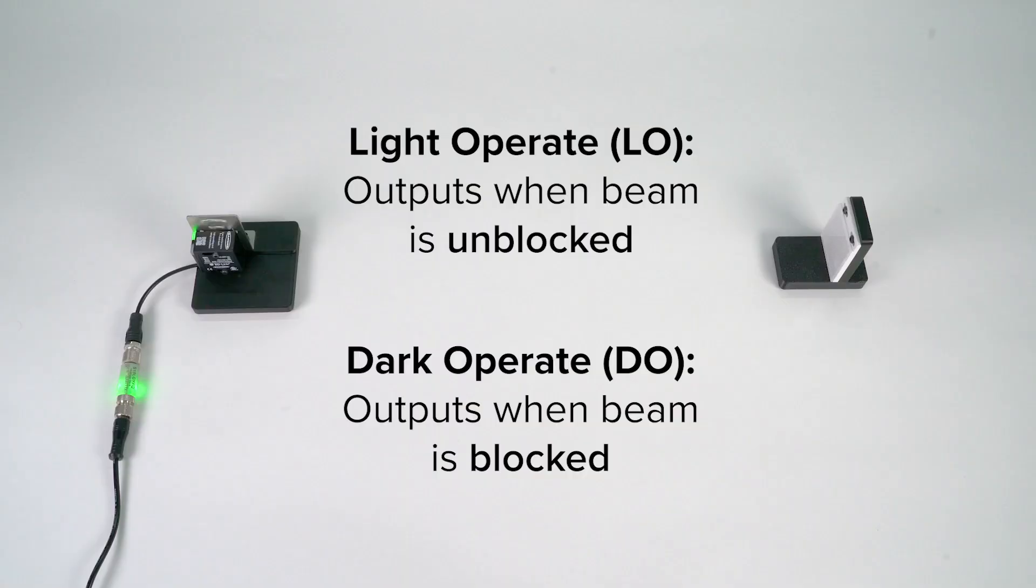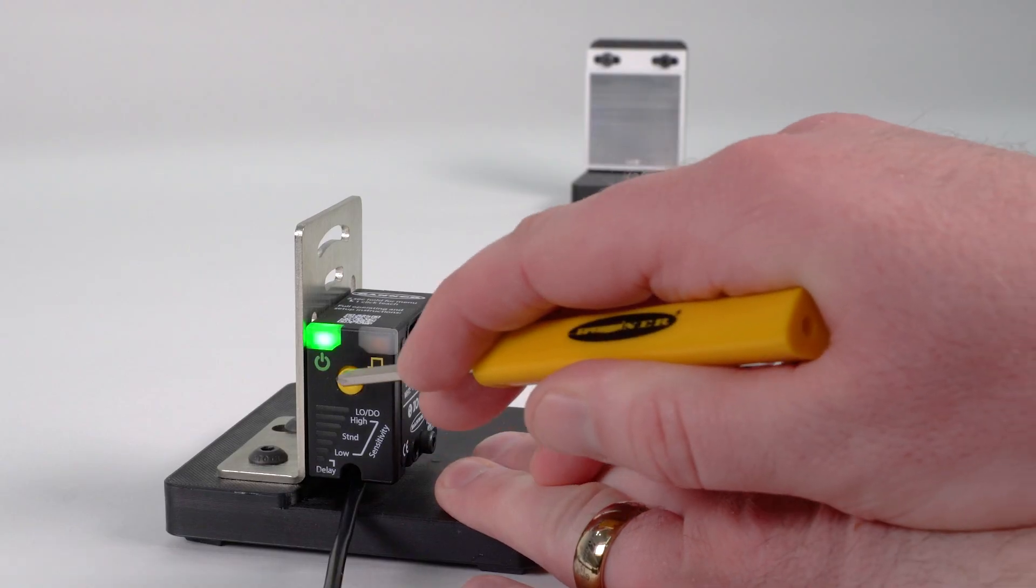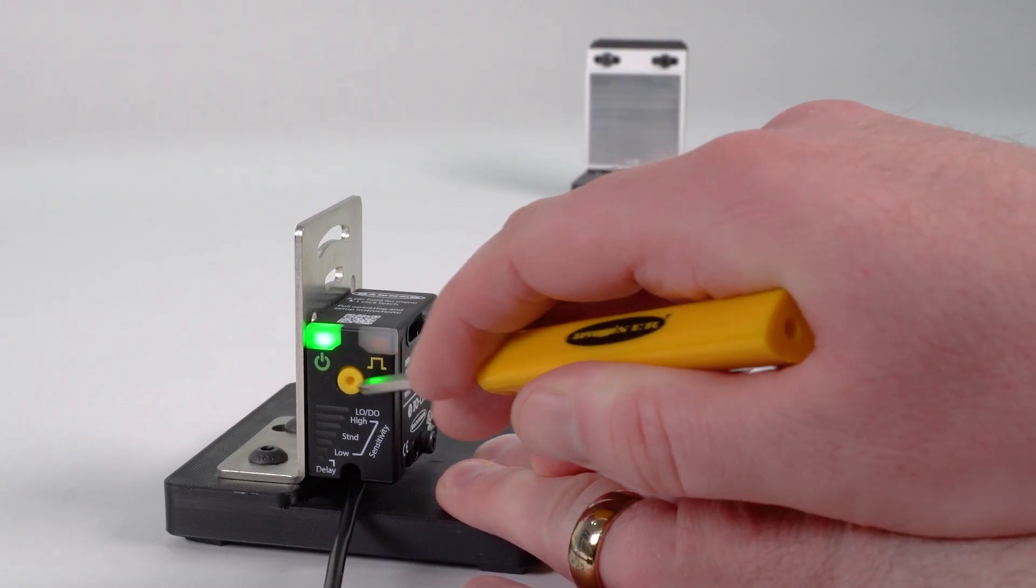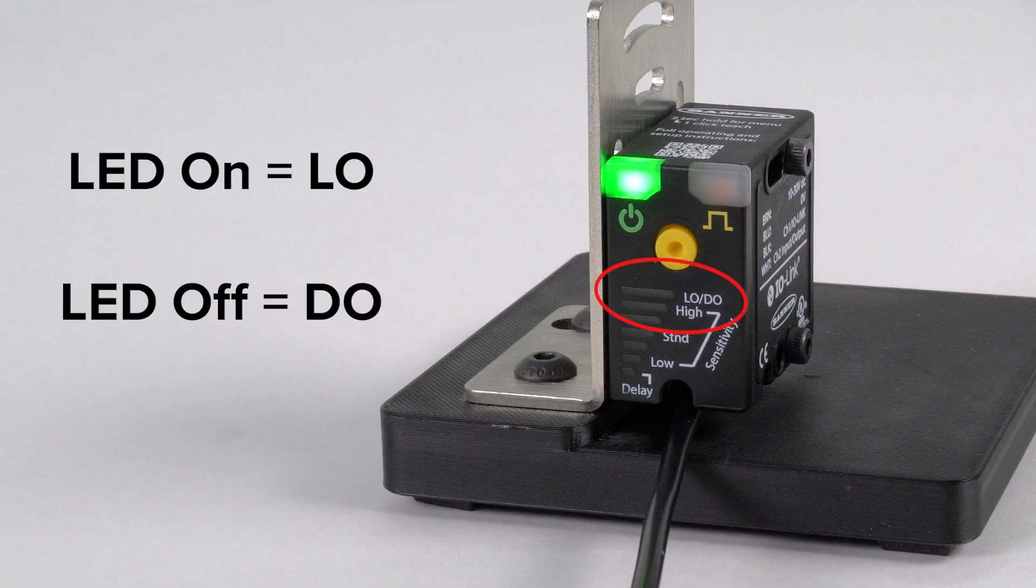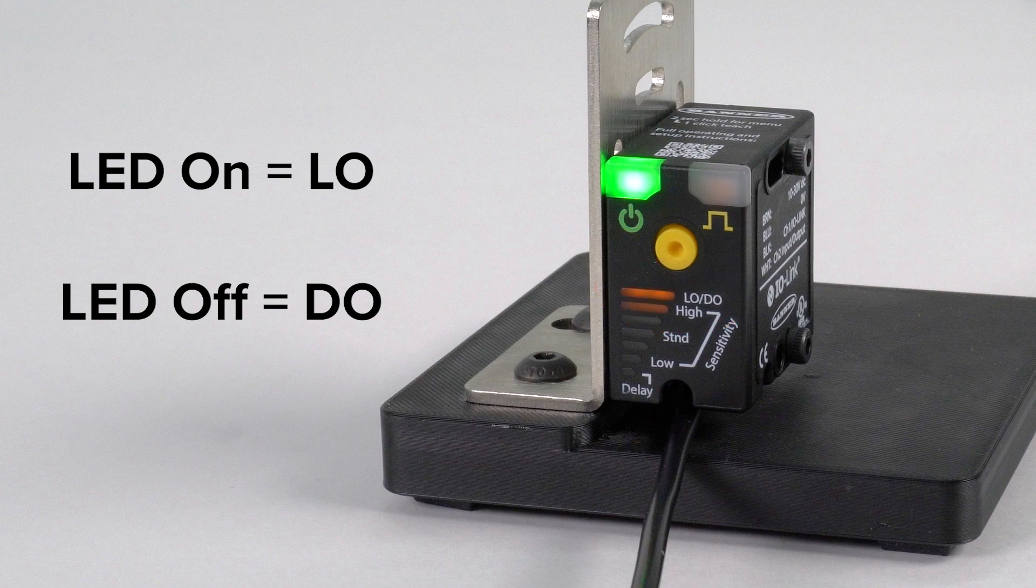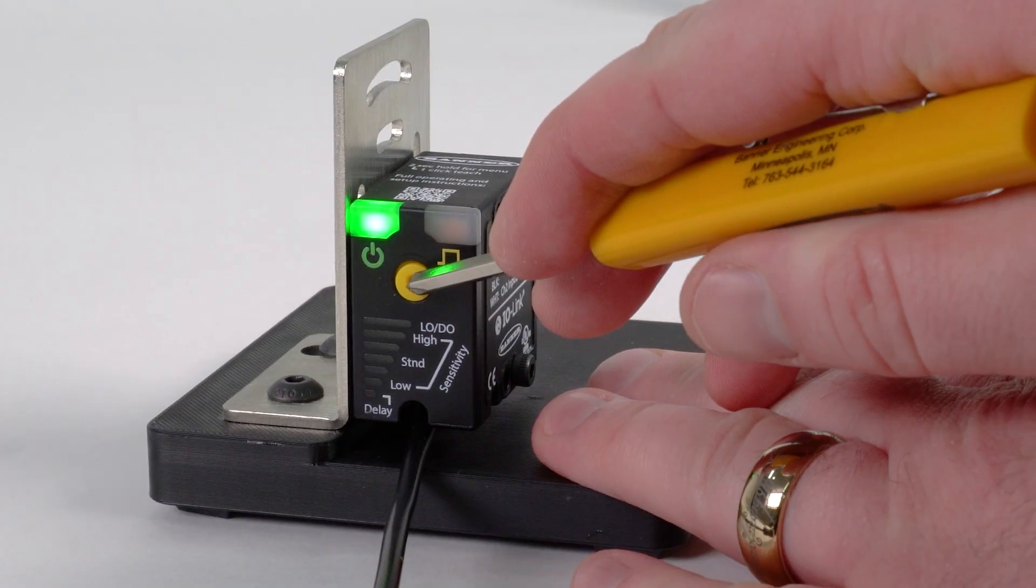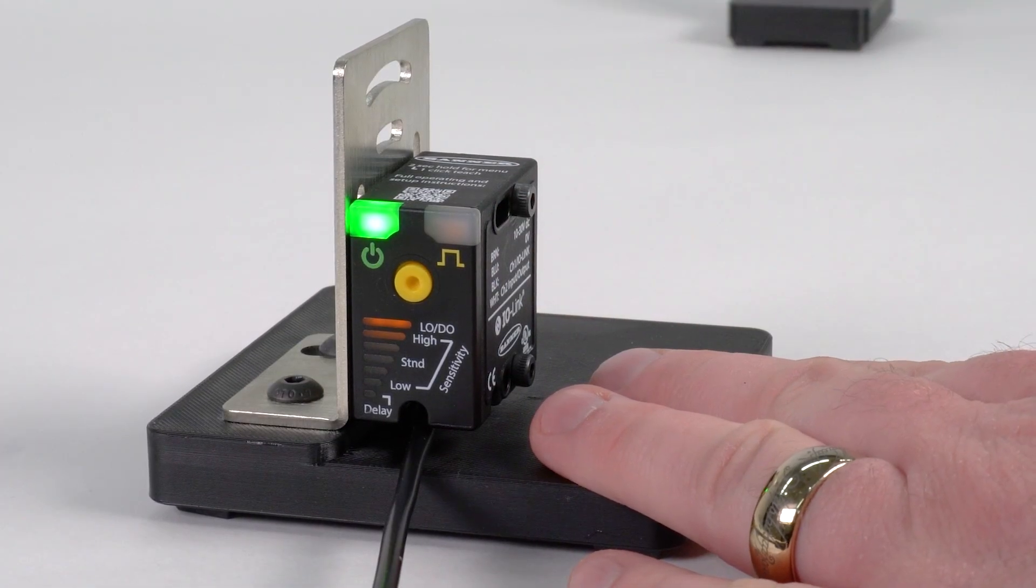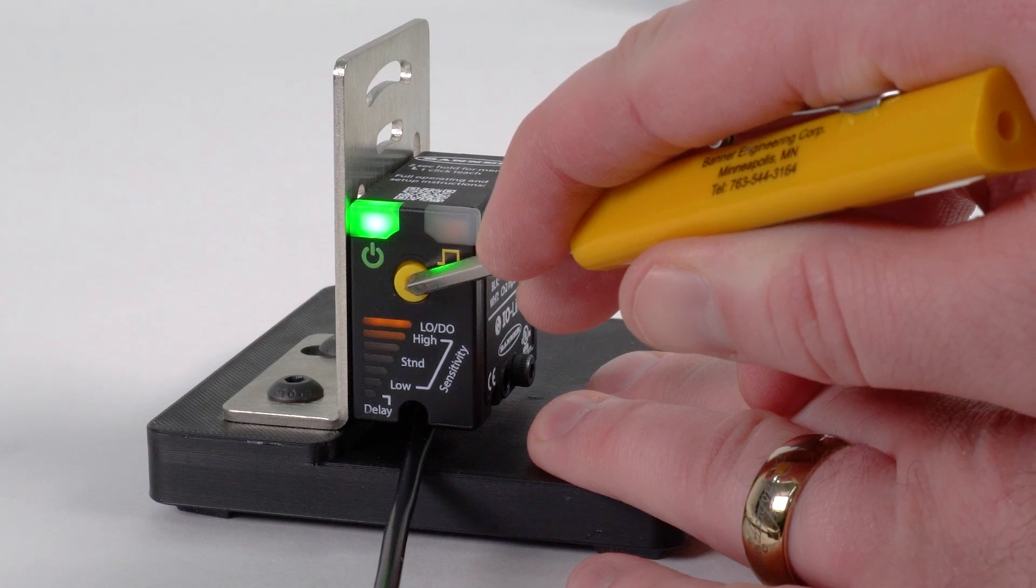If you need to flip which condition triggers the sensor output, you can do so by toggling between light operate and dark operate. To do this, put the sensor into configuration mode and then press the button four times. The top bar of the bar graph will now show the current output setting with on referring to light operate and off referring to dark operate. Press the teach button to toggle between these options and then press and hold for two seconds to confirm your selection.